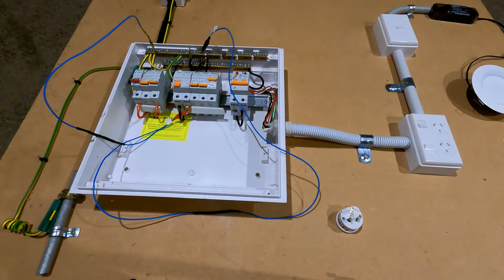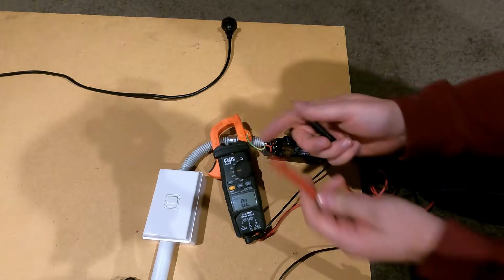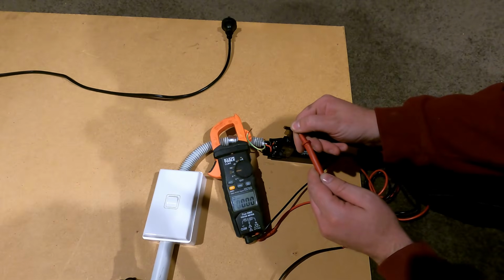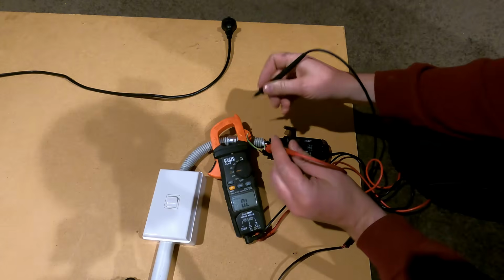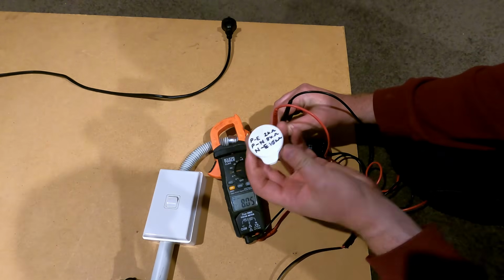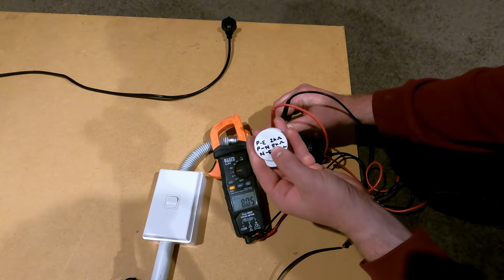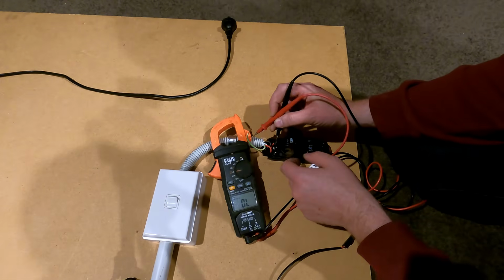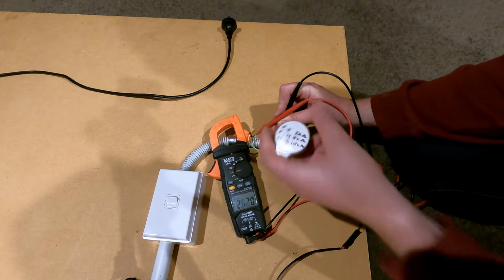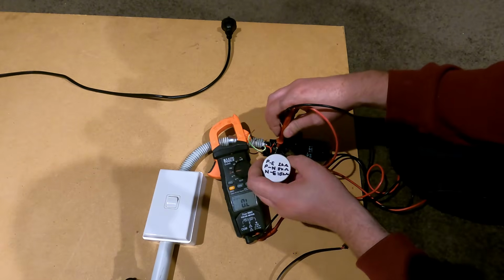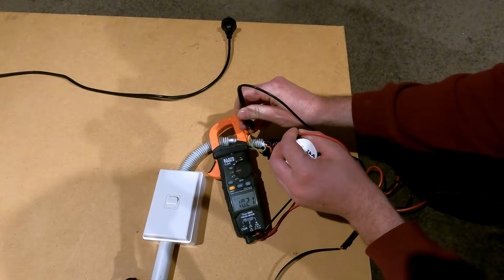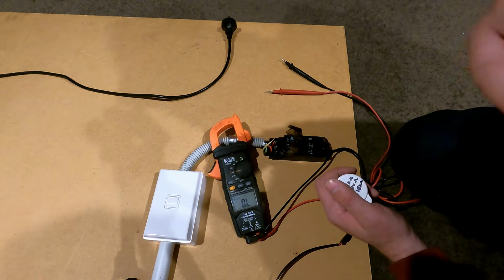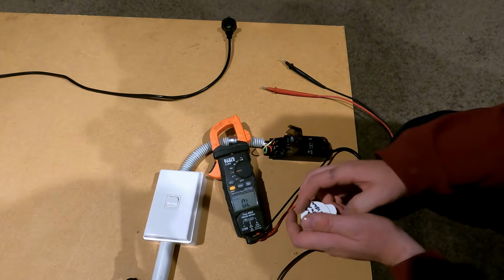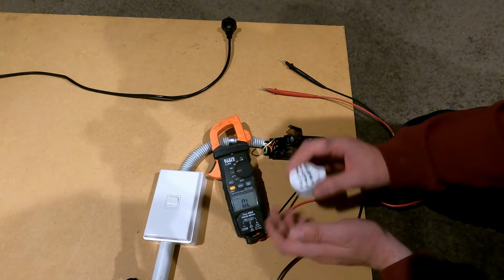From here, turn the light switch on, we'll check the meter again, make sure it's zeroed, and we'll go between phase and neutral. Now we've got 8 kilo ohms, phase neutral, 8 kilo ohms. Go between phase and earth. We've got our 2 kilo ohms, verified on there, 2 kilo ohms, and then neutral and earth, 10 kilo ohms. It works well, it speeds the process up, and I highly recommend that you guys make them.